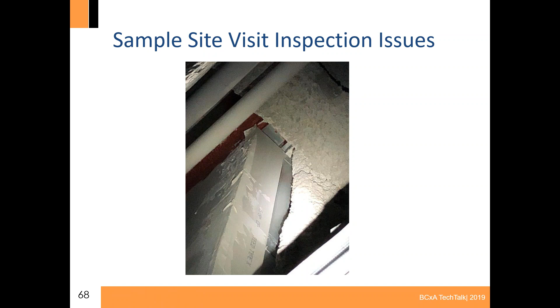Here's another example of standing on the ground and looking up through all of the wire tray and saying, hey, I see a seam there. And again, this is on a rated wall assembly. That doesn't look right. So again, going up on top of a ladder and looking above the duct, we again see that truly the rated wall is not seamed with the mud and the screws are not covered.